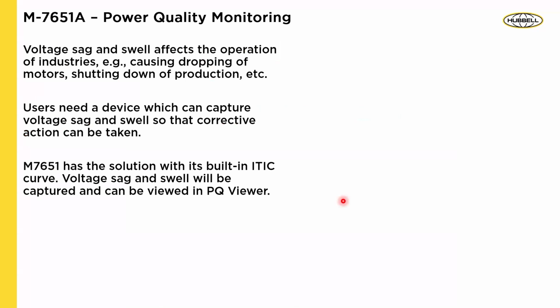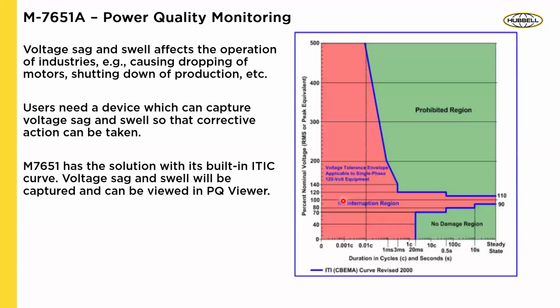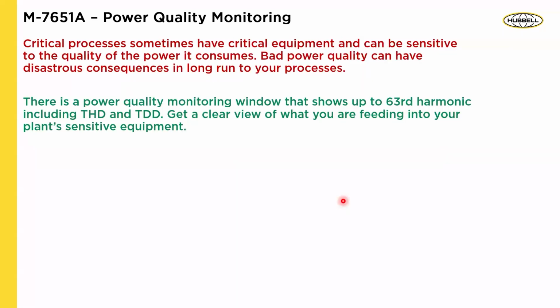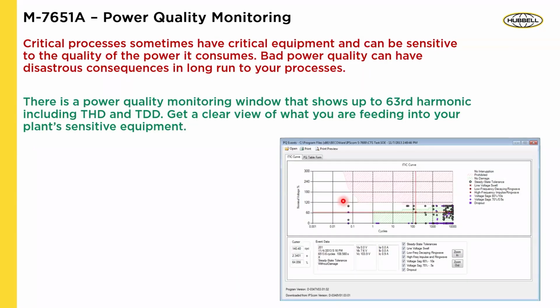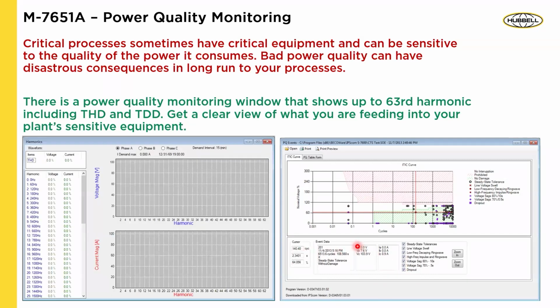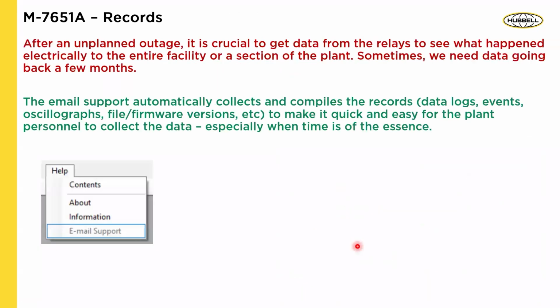The other is the power quality side, right? So you have to know what you're feeding into your plant, because that could lead to long-term damage to your processes. And there's a CBEMA curve that shows you where the no damage region is, the interrupting region, and a prohibited region. So we give you that information. So what we've done is we've tabularized it, we've plotted it on an ITIC curve, and when you select one of these points, it gives you a detail of what kind of event it was. And then you could also see the harmonics visually.